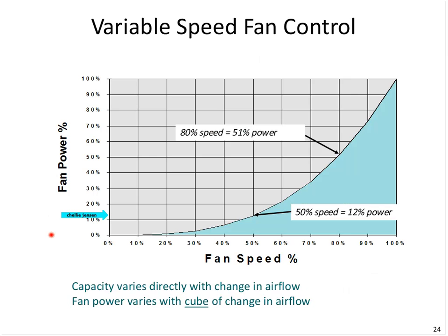In some cases, that's kind of asking a little too much. In other cases, it seems like we get adequate throw. And we have seen situations where the pallets are lined up in such a way that it increases the air circulation rather than blocking it. But in a lot of applications, 70% speed is maybe the lowest speed you would consider. And that gets substantial energy savings.